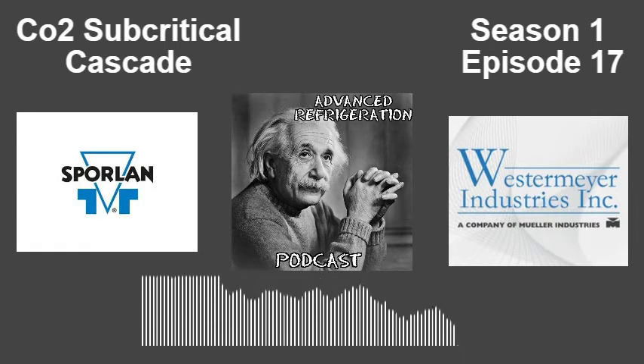So, we were talking a little bit about Emerson. There are other case controllers that do the same thing, basically just modulate superheat and adjust per what you're trying to accomplish. RDM, they are using a temperature sensor on the suction line, obviously, but also on the distributor tubes. Years ago, Emerson made a case controller called the CC100, and that's basically how it figured out its superheat. Because your distributor tube is going to be your saturated temperature of your refrigerant.